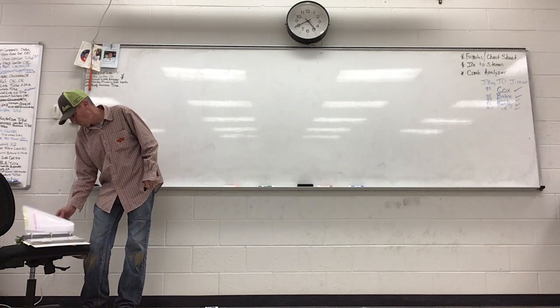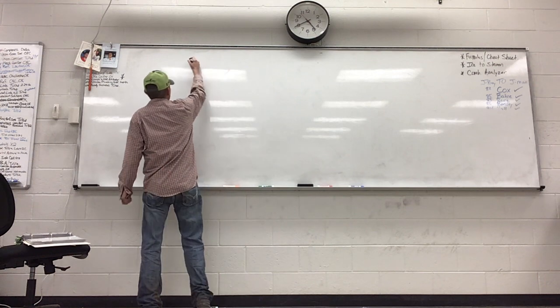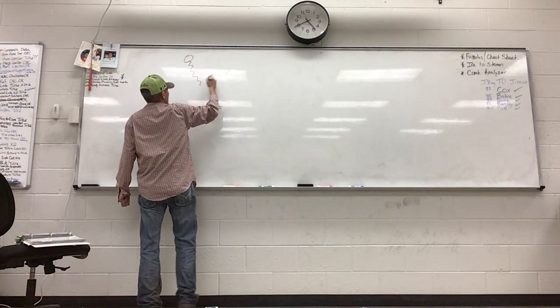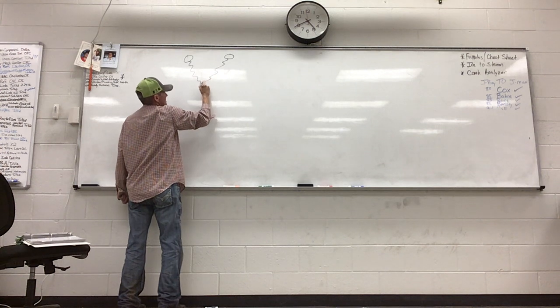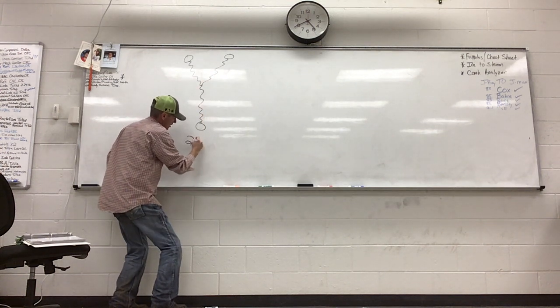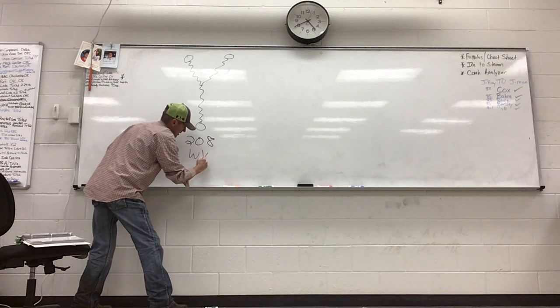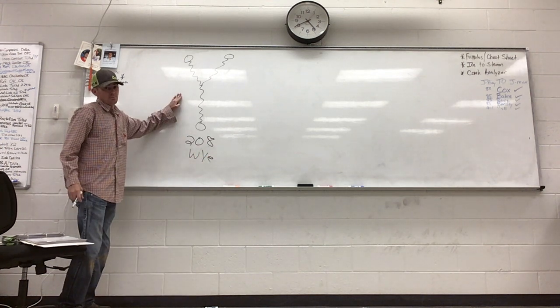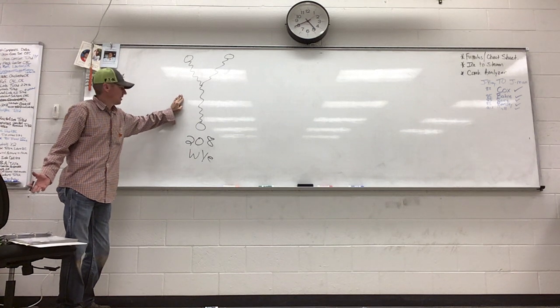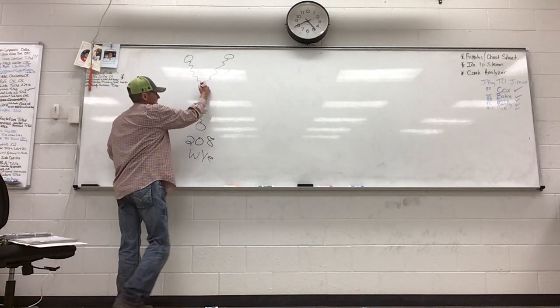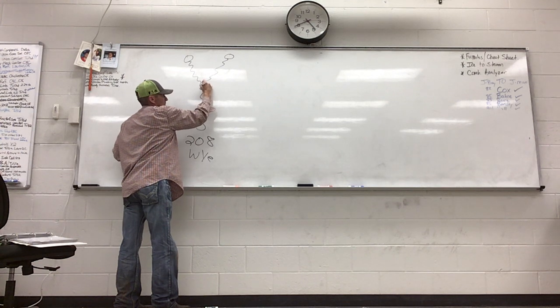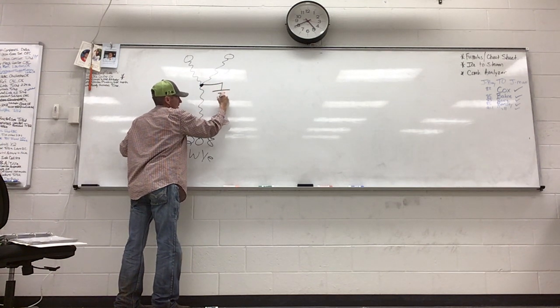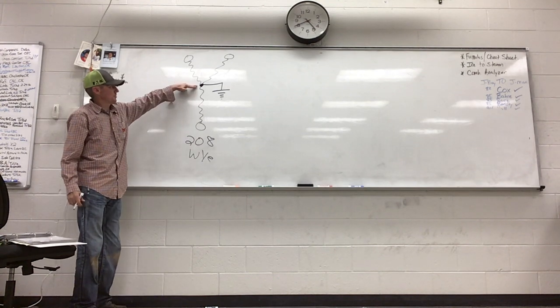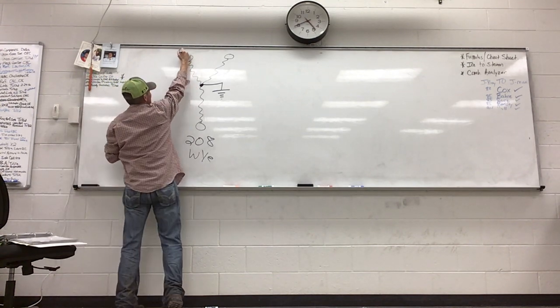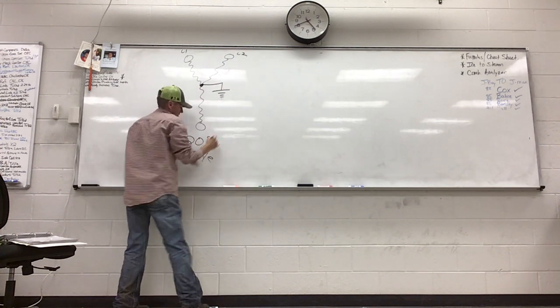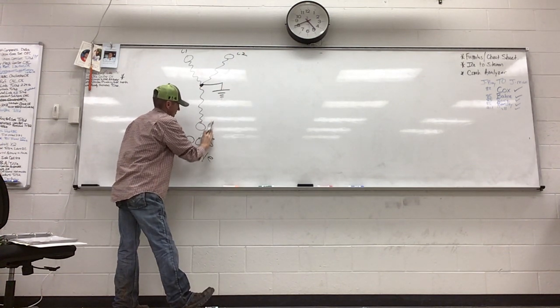On a 208 building, it will be a Y transformer. So on a 208 building, your transformer is going to look something like this—this is a 208 Y transformer. Right now it just looks like a typical Y configured motor, but on the transformer, our neutral tap is going to be right there. So let's assign these some names: L1, L2, L3.